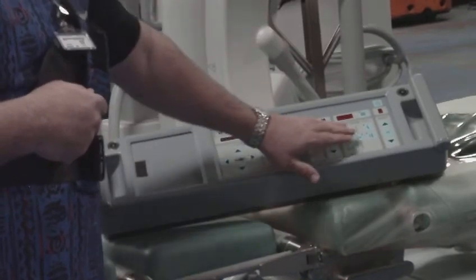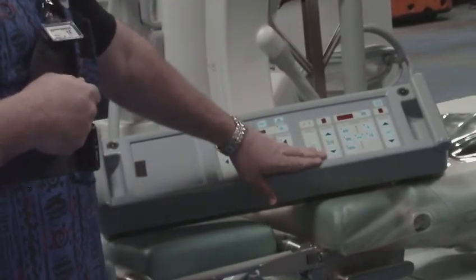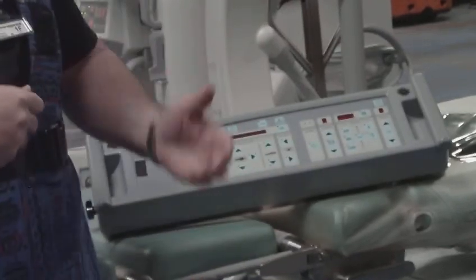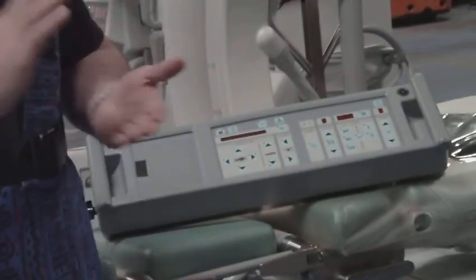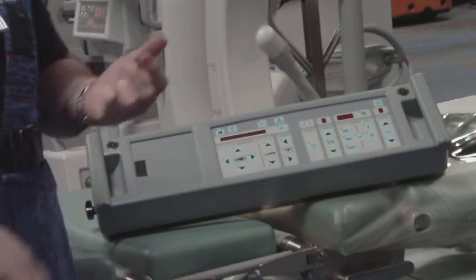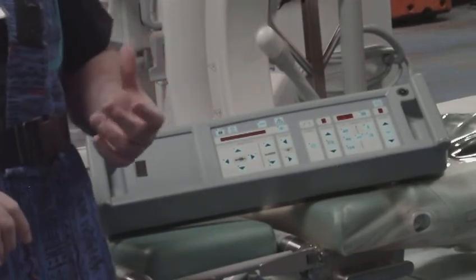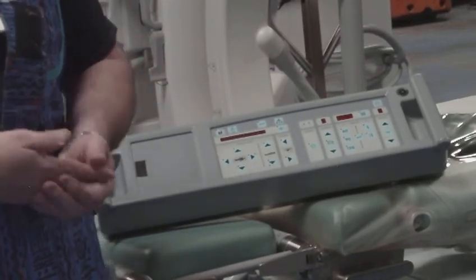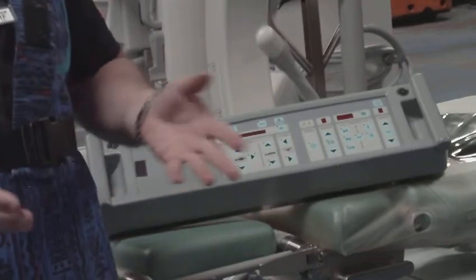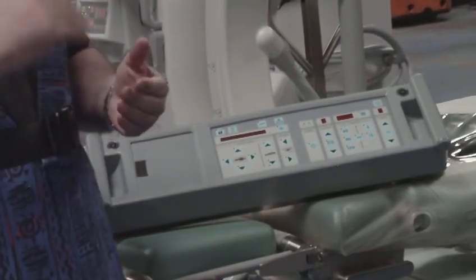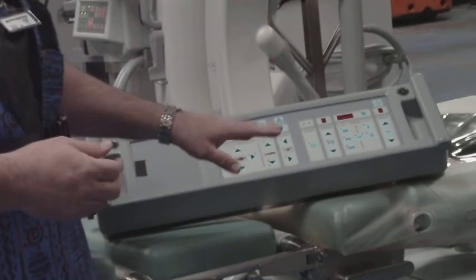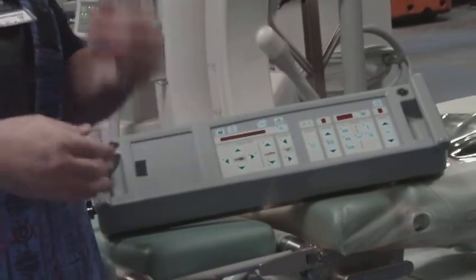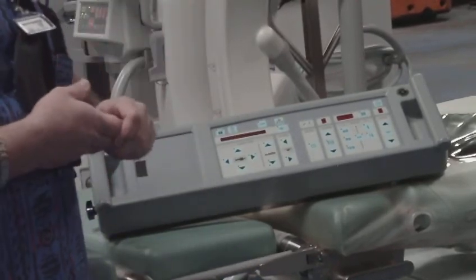With the energy that you deliver, the amount of energy that you put in, we recommend you start at level 3, because you don't want to start at a higher level, because immediately the patient, even though the patient's asleep, they're still going to feel it. So you want to gradually go up. We usually do 50 shocks at each level, and then we slowly move our way up.